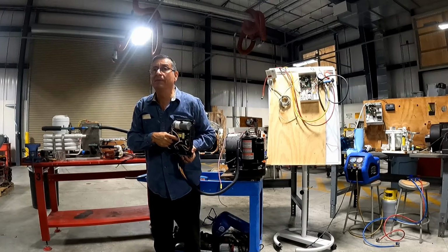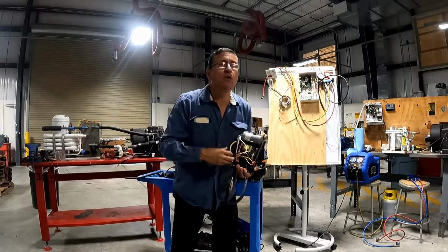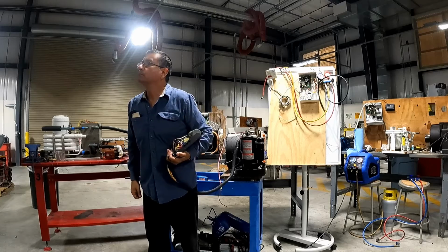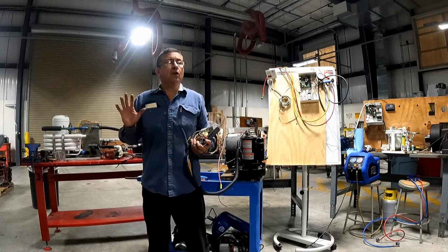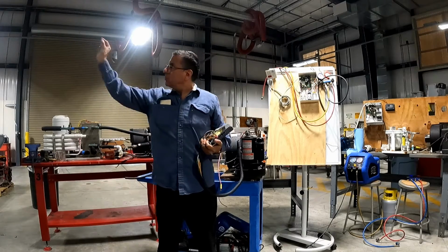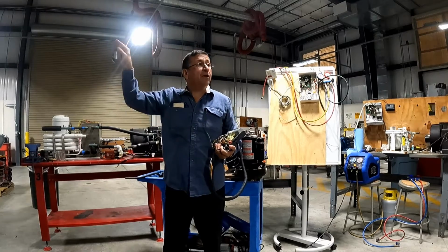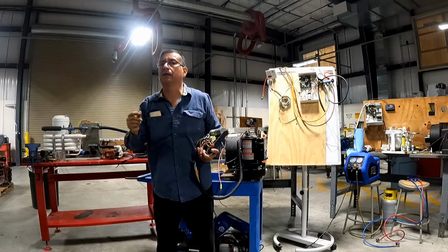Everybody follow me? Pay attention. What is the symptom when you have a problem with the triac? You have electricity going through the entire time if it is broken. You say, Mr. Lopez, the breaker is perfect. 120, the power is good. I have power on both sides of the breaker.